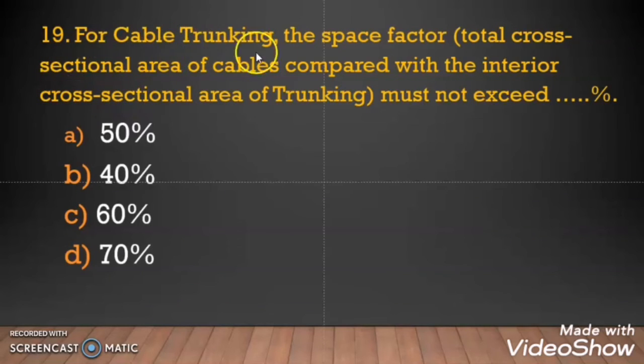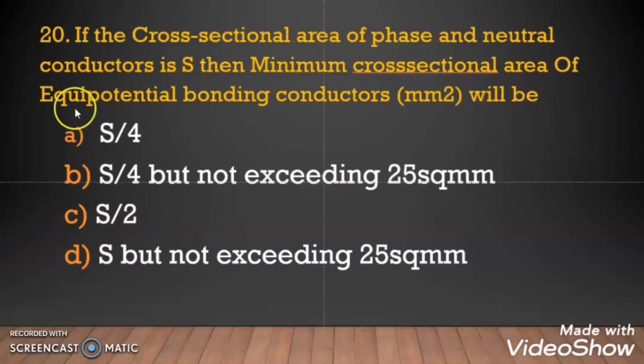Question 19: For cable trunking, the space factor — the total cross section area of the cables compared with the internal cross section area of the trunking — must not exceed? The question asks how full the trunking can be. The correct answer is 60%. Maximum allowed cables in the trunking is 60% full, and 40% should be empty. So the answer is 60%, option C.